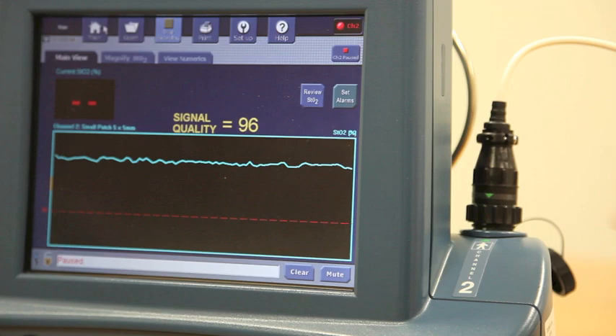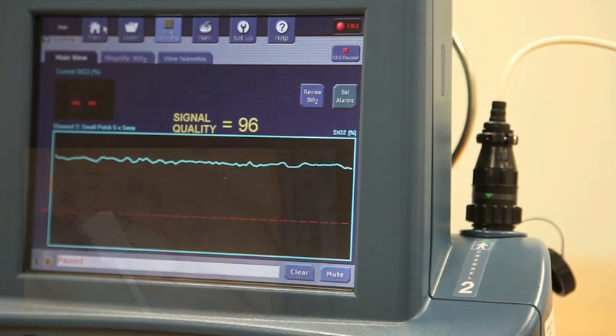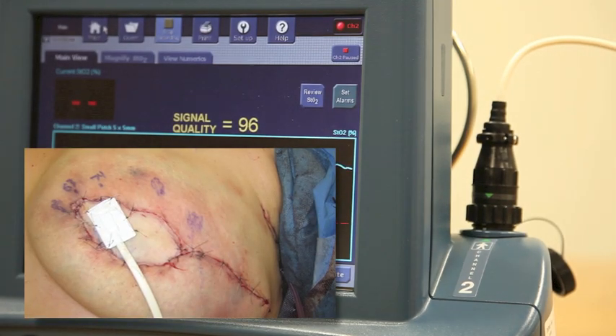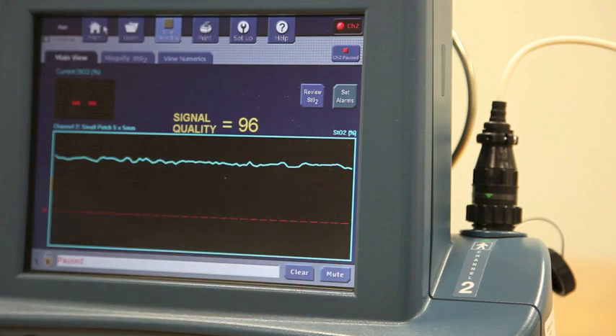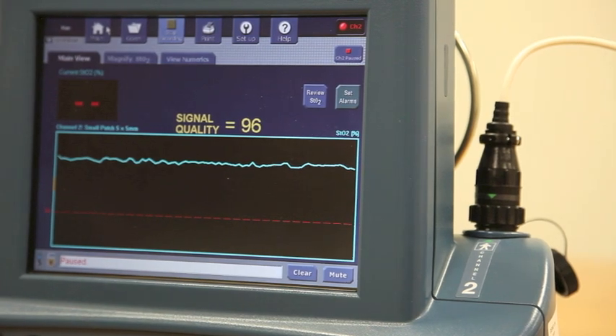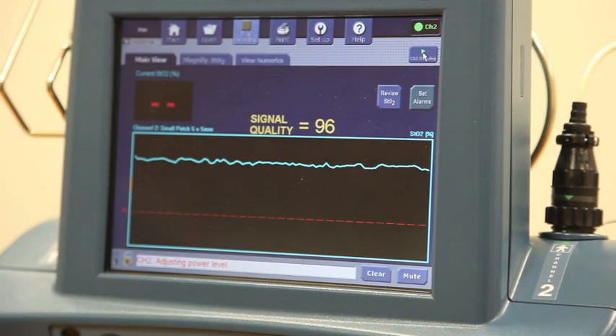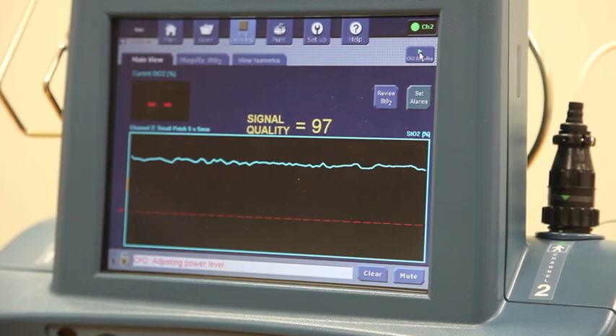Now that the sensor has been connected, the monitoring screen will appear. You are now ready to begin patient monitoring. To begin the monitoring process, make sure the metal sensor head is firmly attached on the cleaned and unobstructed area of the skin. That will ensure a good contact for tissue monitoring. Once the sensor is attached and ready, press the red square button to begin monitoring. Notice the red square has become a green arrow. This indicates the monitor is recording.